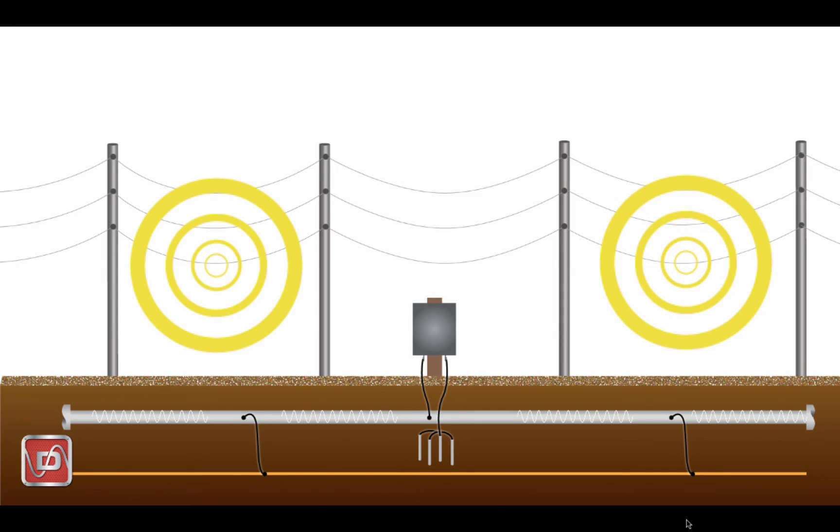Unfortunately, direct bonding zinc like we've done here will negatively impact your cathodic protection system. You will likely see an effect upon your CP system voltage levels and current will be exchanged.